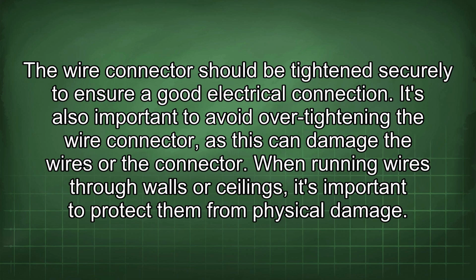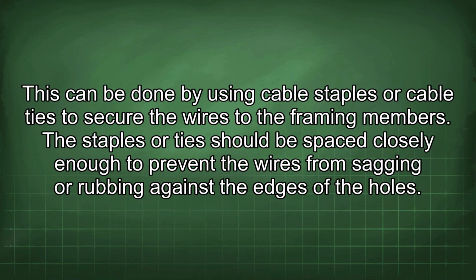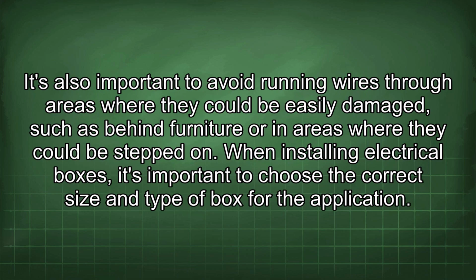When running wires through walls or ceilings, it's important to protect them from physical damage. This can be done by using cable staples or cable ties to secure the wires to the framing members. The staples or ties should be spaced closely enough to prevent the wires from sagging or rubbing against the edges of the holes. It's also important to avoid running wires through areas where they could be easily damaged, such as behind furniture or in areas where they could be stepped on.